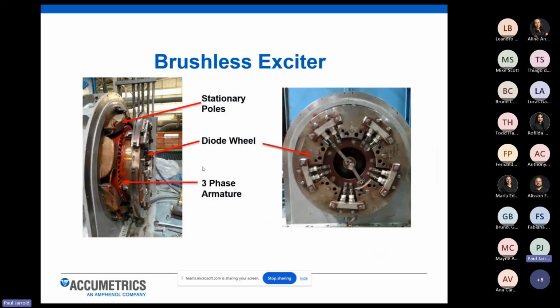They bring across AC voltage, which is induced on the brushless exciter. That is converted back into the DC field voltage through diode wheels or silicon rectifiers that are mounted on the brushless exciter, which convert the AC voltage back to DC voltage to be fed into the generator field windings. So on a brushless exciter, there's no means to gain direct access to that DC field. It's a little more complicated to monitor for ground faults on a brushless exciter. That's where Accumetrics comes in, and that's what we specialize in doing.